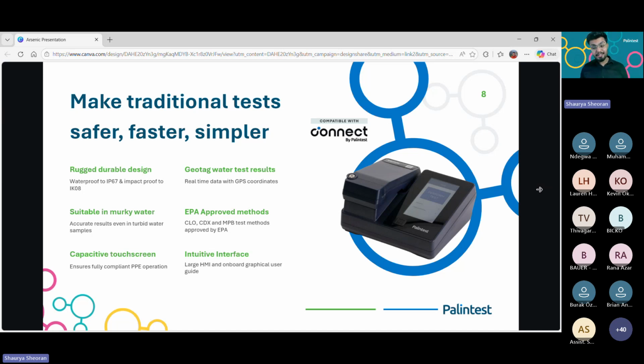And it features several EPA approved methods. EPA is the US regulatory body, the Environmental Protection Agency. It has approved some of the test parameters and testing methods, like chlorine dioxide and lead, as approved methods on this instrument. And finally, you can also geotag the results. You perform the test, you get the results in 2 minutes, and then you upload that data so you have the GPS coordinates of the test result, and you have the test result and the location.